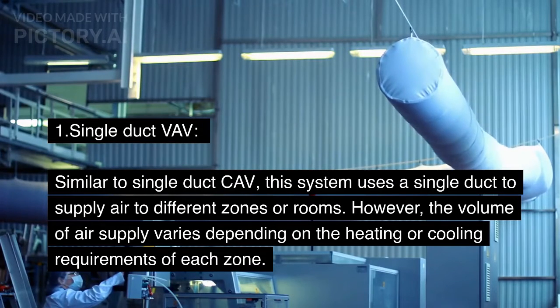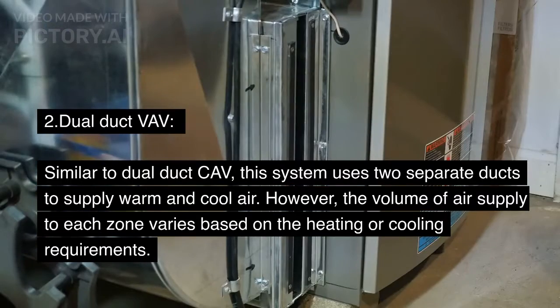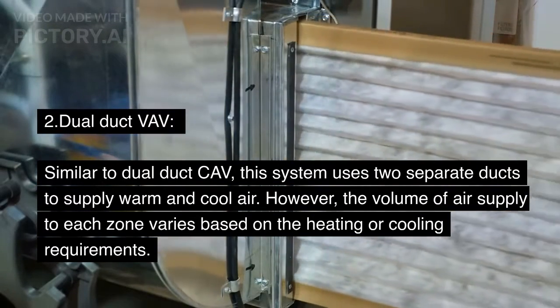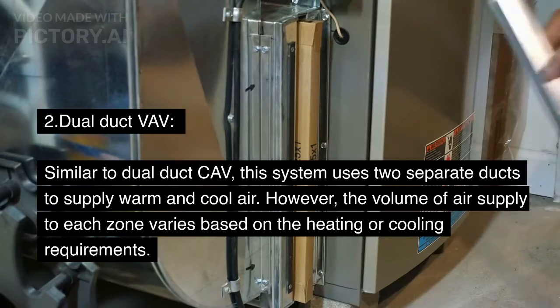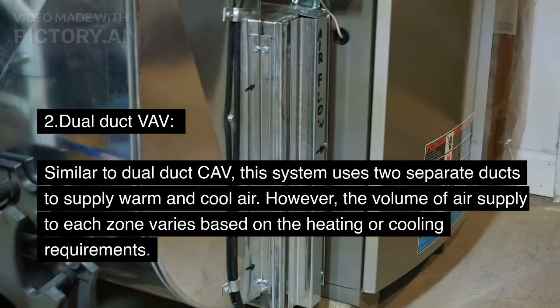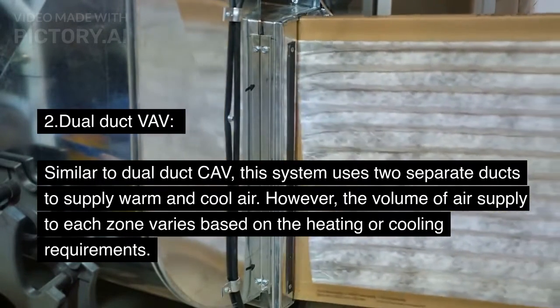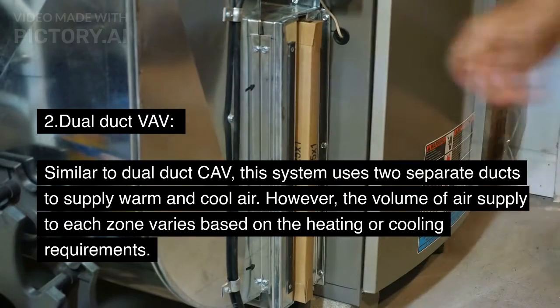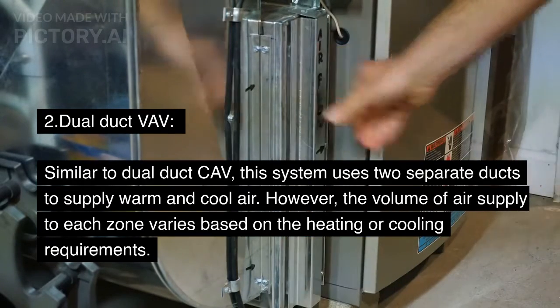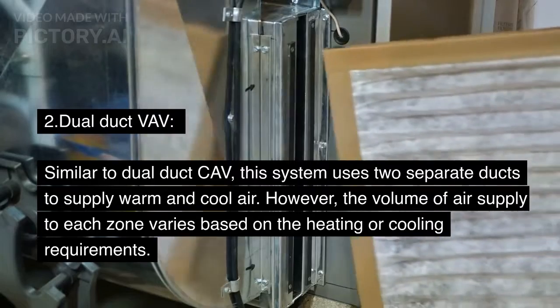1. Single duct VAV. Similar to single duct CAV, this system uses a single duct to supply air to different zones or rooms. However, the volume of air supply varies depending on the heating or cooling requirements of each zone. 2. Dual duct VAV. Similar to dual duct CAV, this system uses two separate ducts to supply warm and cool air. However, the volume of air supply to each zone varies based on the heating or cooling requirements.